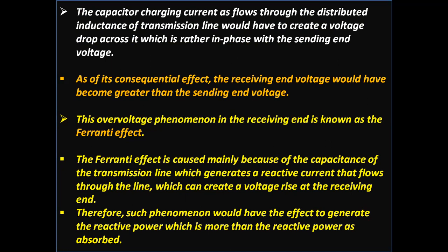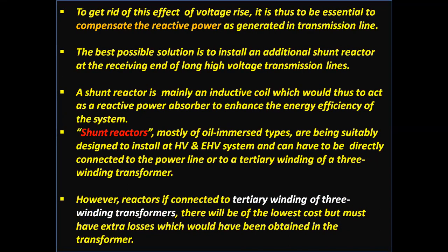The Ferranti effect is caused mainly because of the capacitance of the transmission line, which generates a reactive current that flows through the line and can create a voltage rise at the receiving end. Such a phenomenon generates reactive power which is more than the reactive power absorbed. To get rid of this voltage rise, it is essential to compensate the reactive power generated in the transmission line.